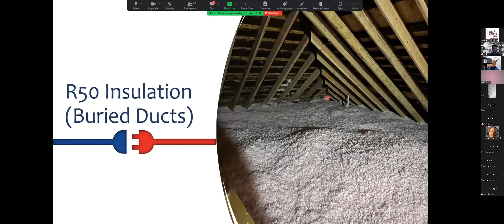This is what the attic looked like after we buried the ductwork. You can see some of the ductwork under here, but this is what we're talking about, full duct burial. When my duct is buried under this type of insulation, this attic can be 140 degrees. I've got R30 on here. I'm not going to use a lot of capacity. It can be really cold up here, and I'm not losing heating capacity through the ductwork. And now I've also gained the thermal benefit of actually having the R50 in the attic.